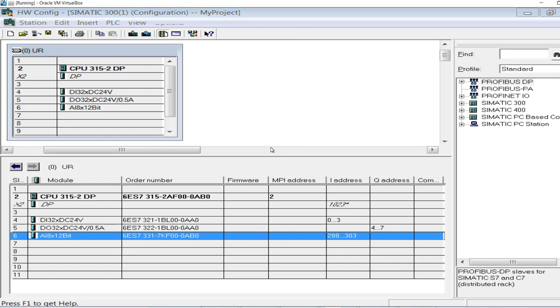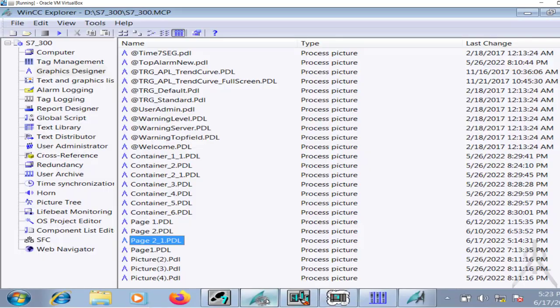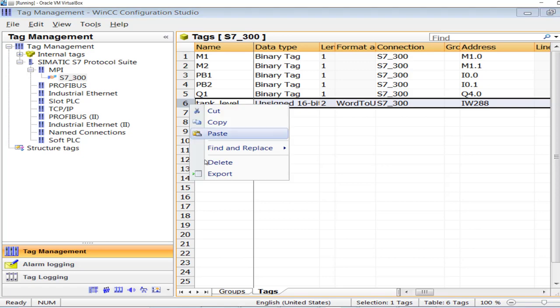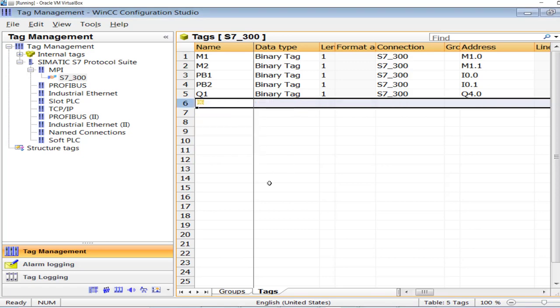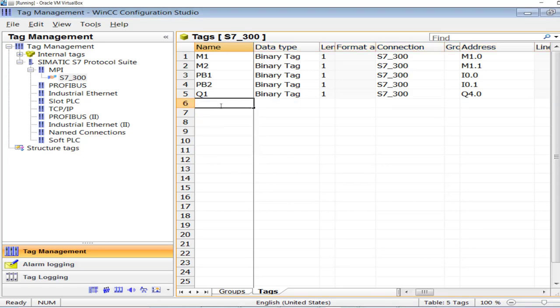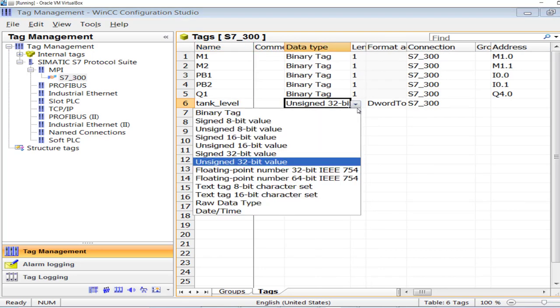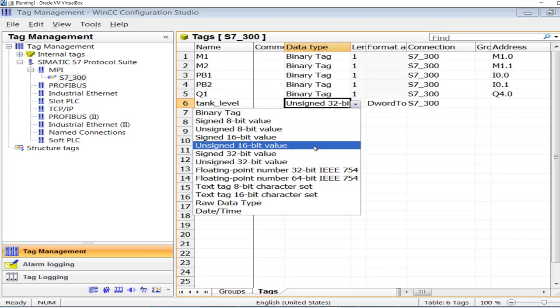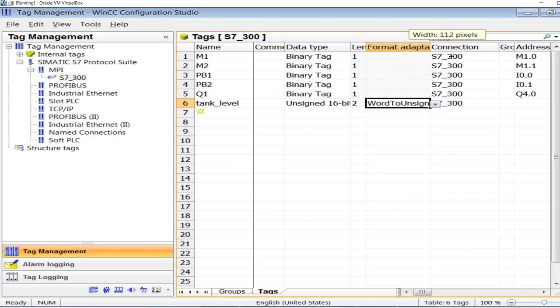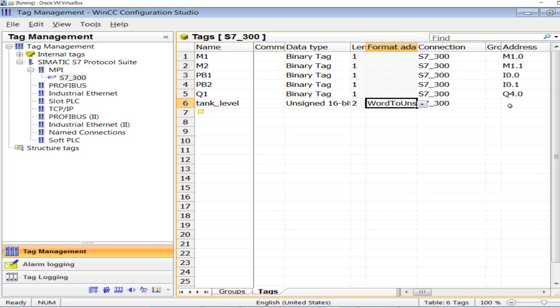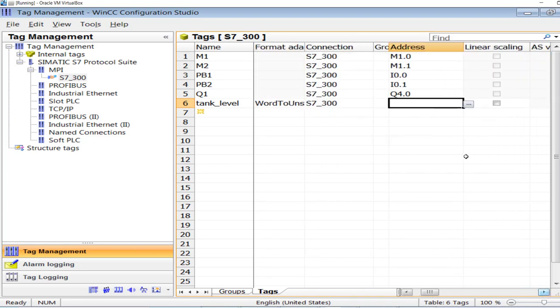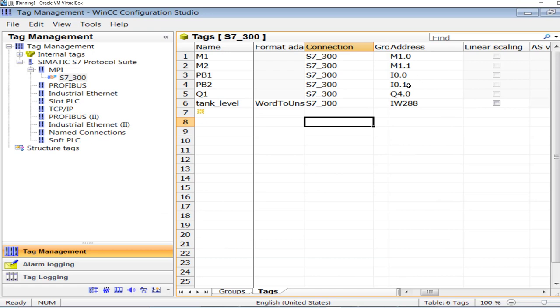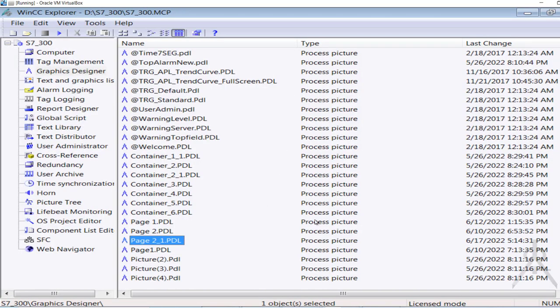So without reinventing the wheel, go to the tag management section. I will add that analog input value or the analog input tag to my tag management section. I will name it Tank Level. That is Word, unsigned 16-bit value. The address is PIW 288. The analog input value has been successfully updated into the database.